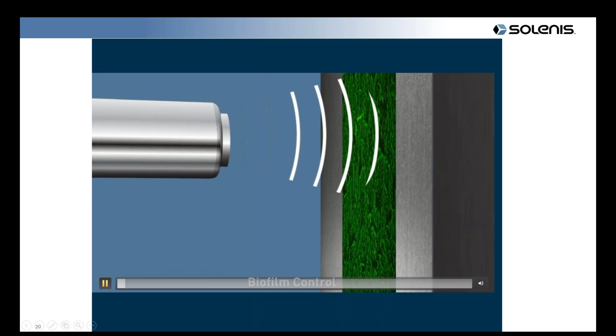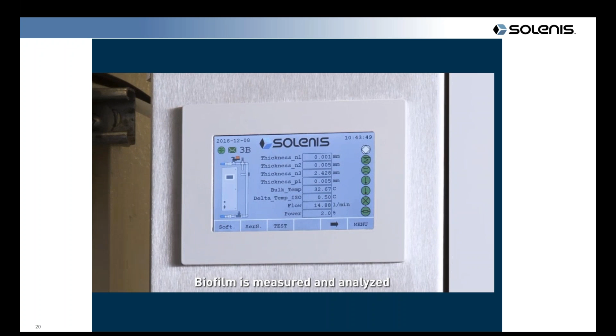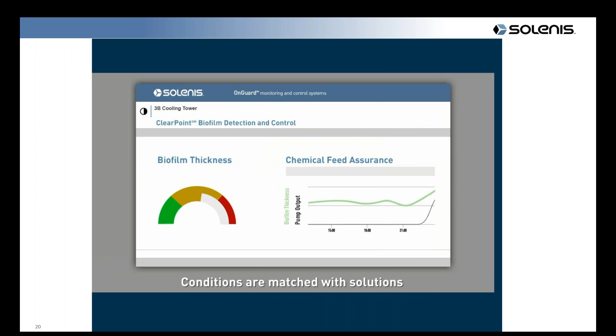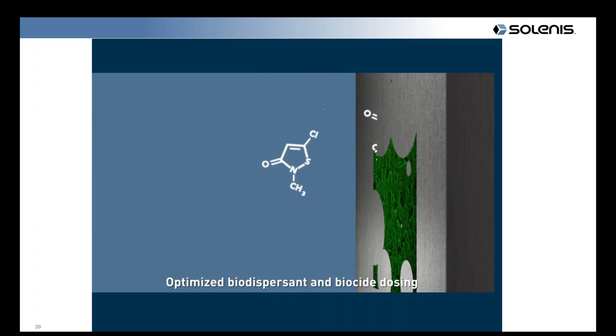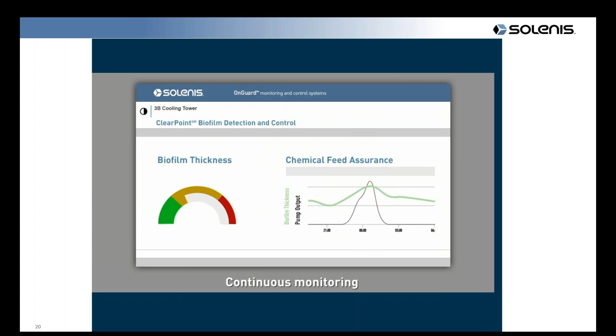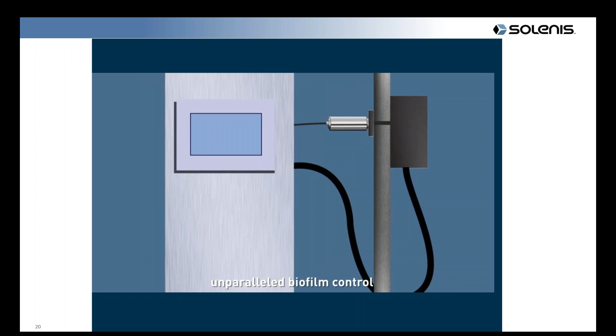Now we see the signal, and it's sensing that we have a biofilm there, and the readout on the screen will show the thickness of the biofilm. If you look at OnGuard Online, the dashboard shows that we've had a buildup. Now we can optimize by feeding a biodispersant or changing our biocide dosage, and we can clean it up. You can see that the chemical did feed and the thickness has gone down.